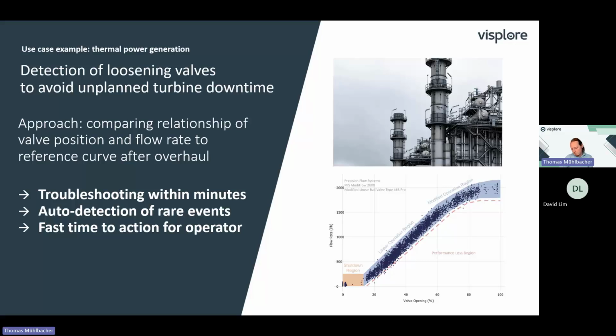If the valve is starting to be clogged or coming loose, then the flow may be too much or too little compared to what you would expect from the recorded valve position. If such a thing is not recognized early, it may lead to a major maintenance need.